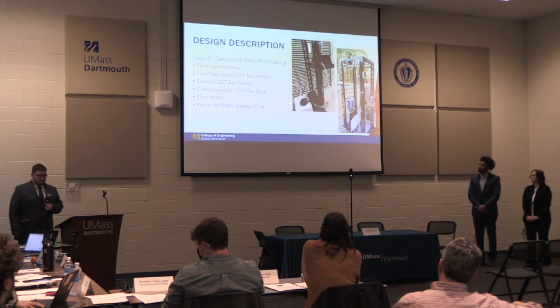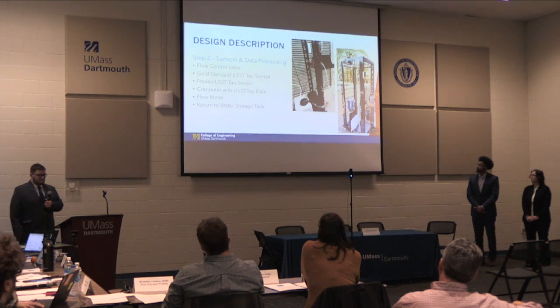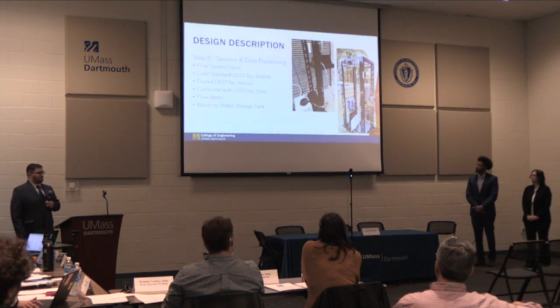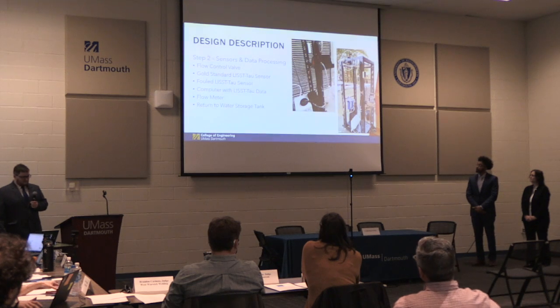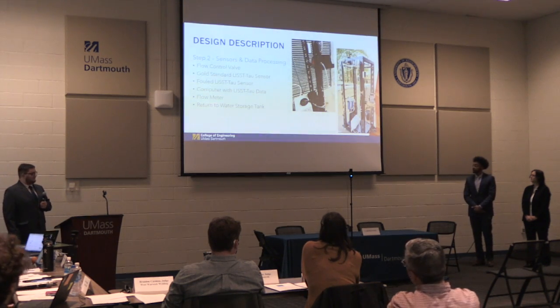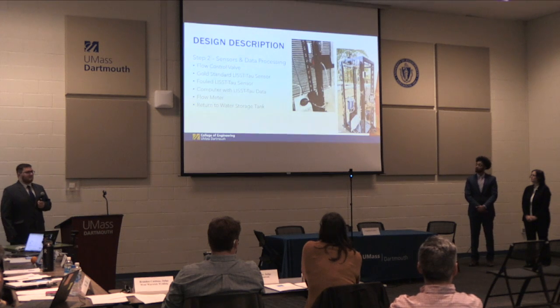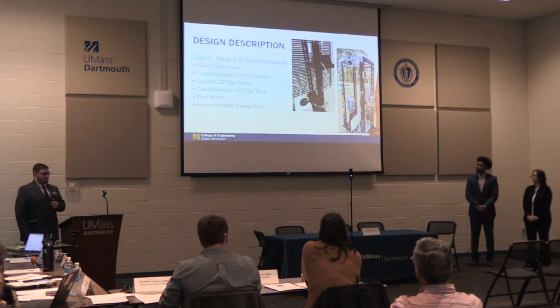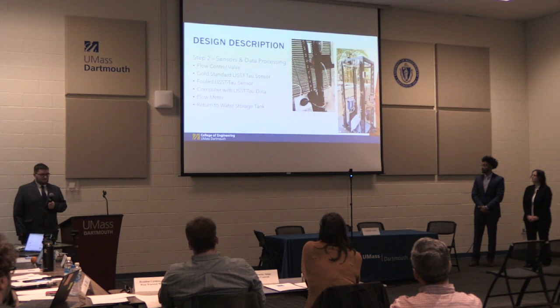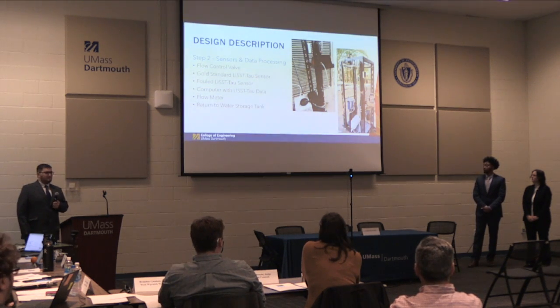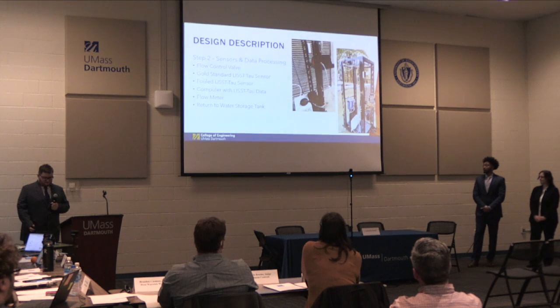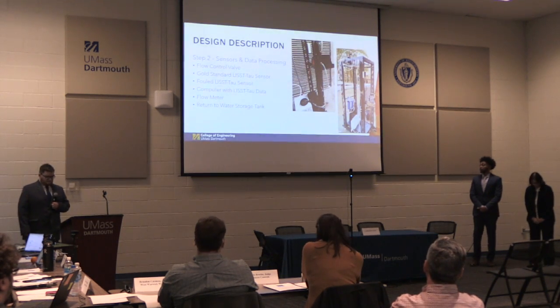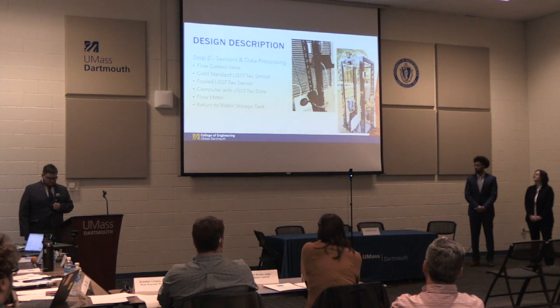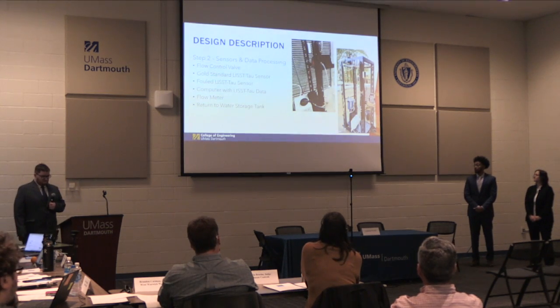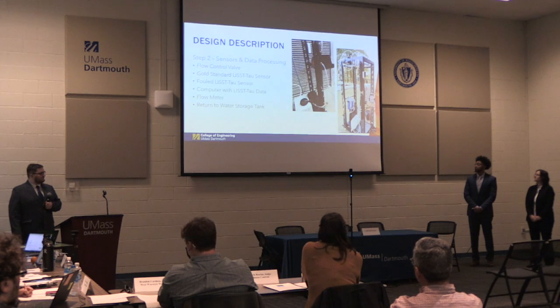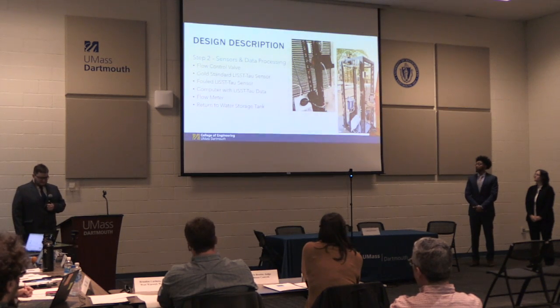And then to our fouled LISST-Tau sensor, which is our device under test, to compare the 2 readings, which are displayed on the laptop, to get a good idea of how well the device that's returned from the glider is still functioning and whether or not it can go for another deployment or if it needs to be sent back to the manufacturer and recalibrated. And once it comes out of that fouled LISST-Tau sensor, it goes through our flow meter just to verify the flow rate that's passing through the sensors is within that 2 to 4 liters per minute, and then it is returned to the bottom water storage tank to complete that closed loop.